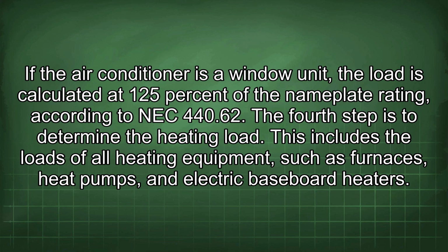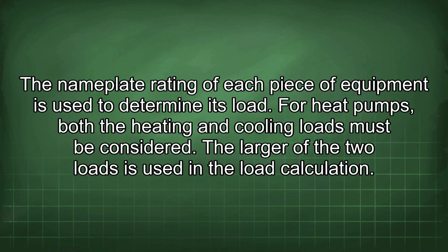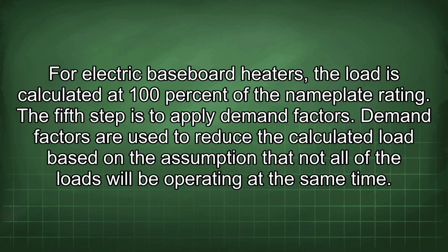This includes the loads of all heating equipment, such as furnaces, heat pumps, and electric baseboard heaters. The nameplate rating of each piece of equipment is used to determine its load. For heat pumps, both the heating and cooling loads must be considered. The larger of the two loads is used in the load calculation. For electric baseboard heaters, the load is calculated at 100% of the nameplate rating.